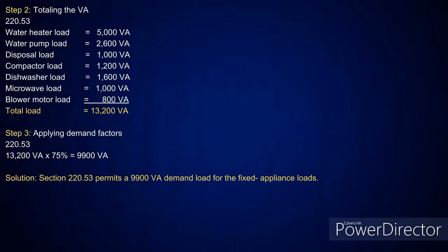220.53, and what it says here, when you pick this up, this is a demand factor of 75% that's applied here. And as you go in and read this, right below it, you're going to see, and this is something I want to point out also to everybody else. When you go look in the 2023 NEC, you're going to see they've got a new item 5 there that says electrical vehicle supply equipment. That'll be one of the loads that will be taken off here. We're going to remove that load from the fixed appliance load.